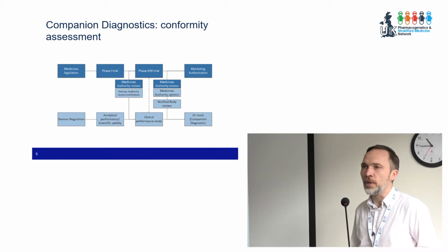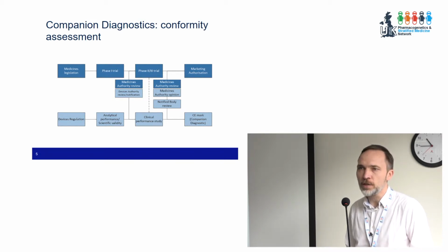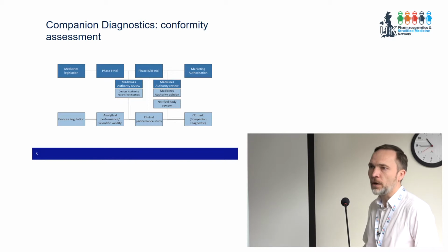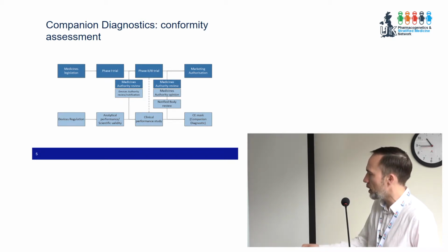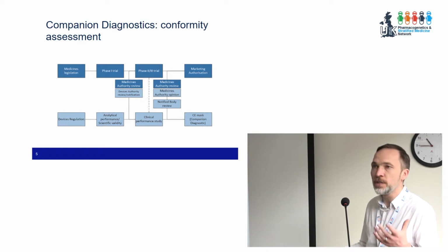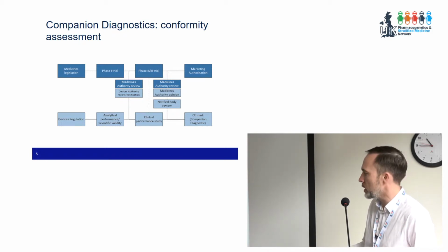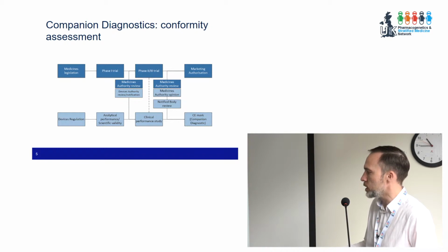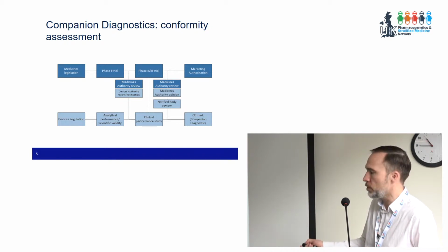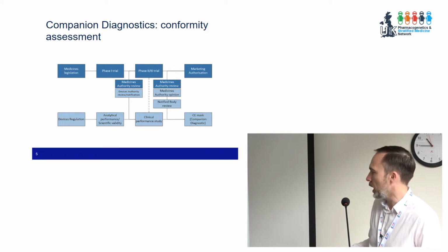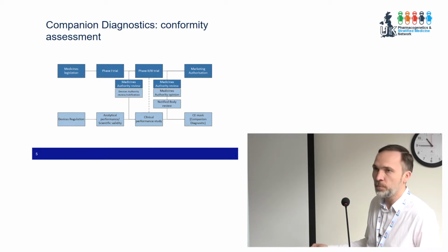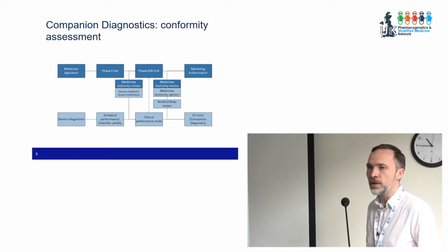Those of you who are involved with medicines and companion diagnostics, this is my kind of take on how companion diagnostics will be regulated. That's pretty much what I've talked about along the bottom there. Again, from an IVD perspective, a companion diagnostic is an IVD. You get your analytical performance and your scientific validity. I'll explain these terms in a moment. You go to the devices authority before you start your clinical performance study, and then you can get your CE mark once you've been to a notified body with a medicines authority opinion.